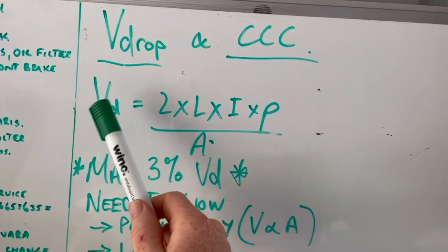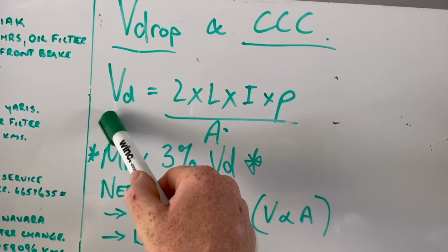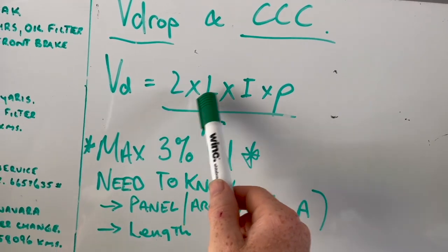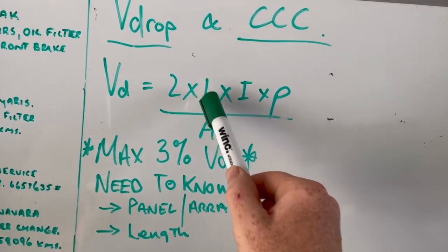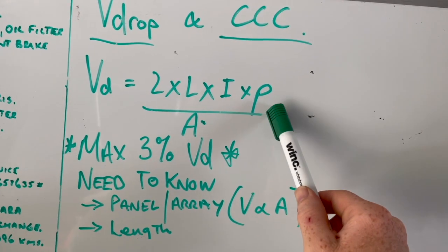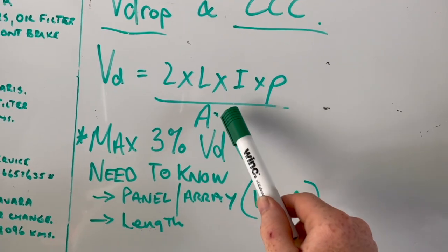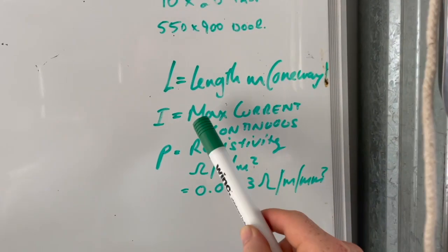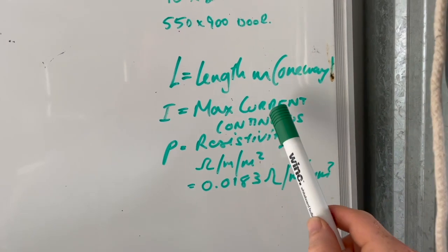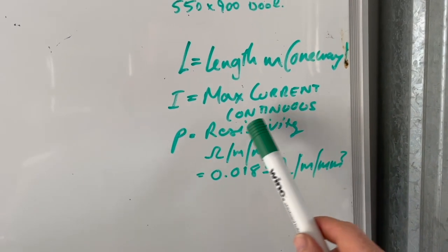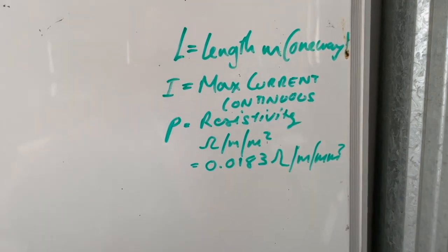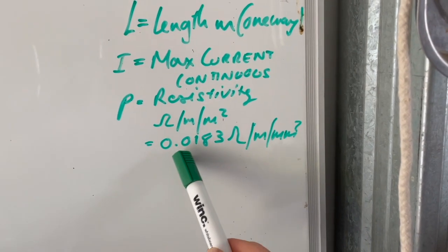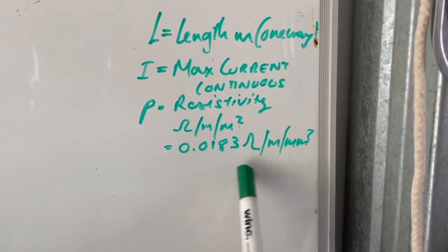This is the formula you need to know voltage drop. That'll give you how many volts drop over this situation, which is 2 times the length of the cable one way, times by I is the current, times by Rho is resistivity, divided by the area, cross-sectional area of your cable. And P is resistivity, which is ohms per meter per millimeter squared. And that standard figure for a copper cable is 0.0183. So that's all we really need to know.